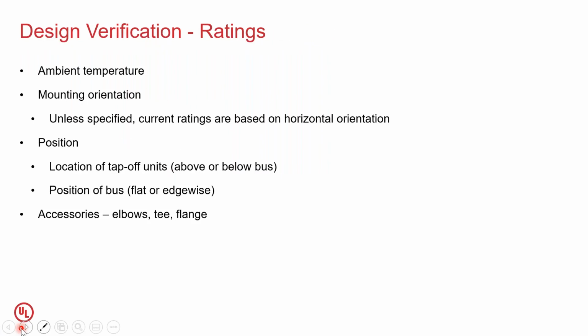A few other ratings we have already gone through, but one thing I would like to highlight here is the mounting orientation, more specific for busways. Unless otherwise stated, this is very important for end users, manufacturers and regulators. The busways are typically tested only in horizontal orientation, unless the manufacturer also declares their busways are intended for vertical orientation. We have seen that in a vertical orientation the temperature rise observed is more than in a horizontal orientation. So just because the sample has passed in the horizontal position does not mean the limits will still be met in the vertical. You still need to do certain tests, like temperature rise, to prove that this particular busway can also be used in a vertical orientation.